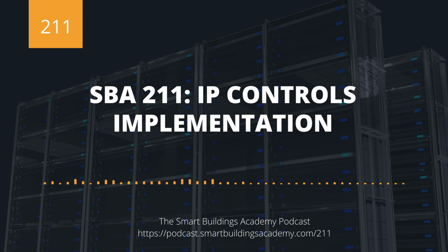The problem is the IT network's not yet in place. So there's your conundrum. If you are implementing this, you're either going to have to delay commissioning and final test until close to the certificate of occupancy, when they start putting the IT gear in place, or you're going to have to implement your own network. That's not something you don't already do. You already implement a network. You just don't implement it at this scale. So just be cognizant.